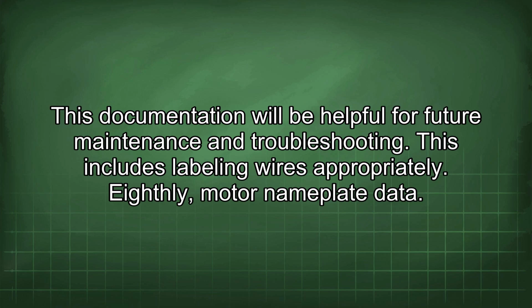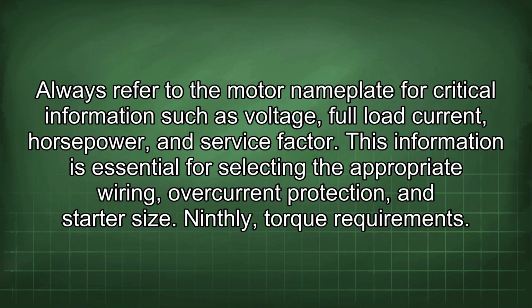Eighthly, motor nameplate data. Always refer to the motor nameplate for critical information such as voltage, full load current, horsepower, and service factor. This information is essential for selecting the appropriate wiring, overcurrent protection, and starter size.